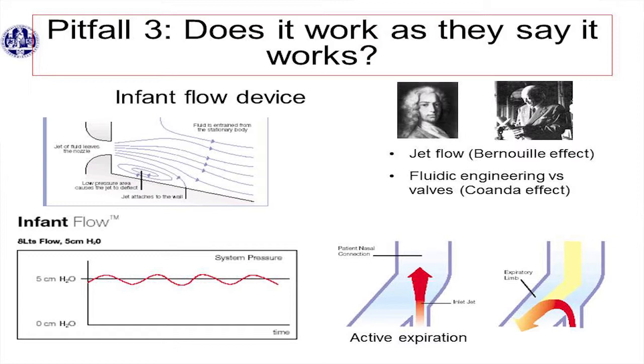And the fluidic flip is so that during expiration there's a pressure increase, and due to the pressure increase here, immediately the angle changes and you get a flip of the inspiratory flow. So the patient doesn't have to breathe against the flow, and it really helps the patient to exhale. So they call it an active expiration, which I think is a misnomer. But it gives you stable CPAP pressure, and it should give you less work of breathing. So this is how they tell you it works, and it really works on the bench tests.